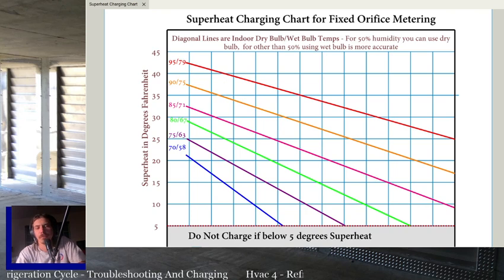because they can get really messed up when you're dealing with an undercharge, with a dirty evap coil, and an inefficient compressor or something like that. You start compounding issues on top of each other, and that's when you're going to be scratching your head for 2 or 3 hours. So if you are having trouble figuring it out and nothing seems to match what you see on these charts or anything like that, just clean the coils, pull out the charge, weigh it back in.